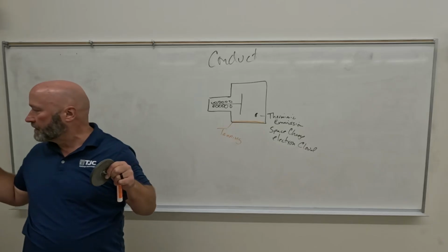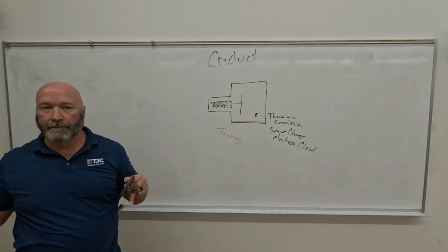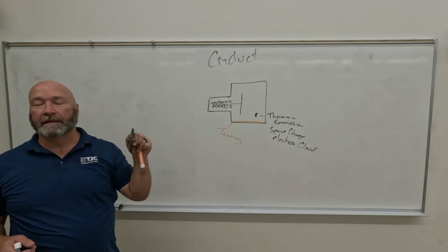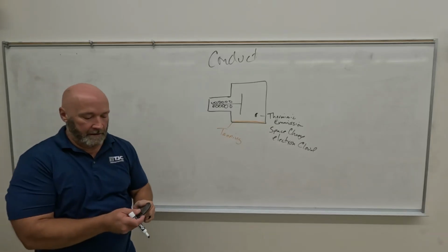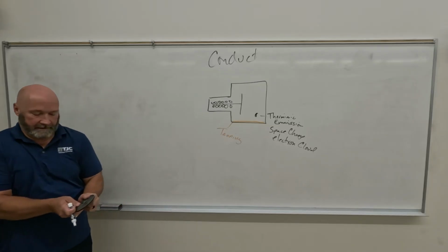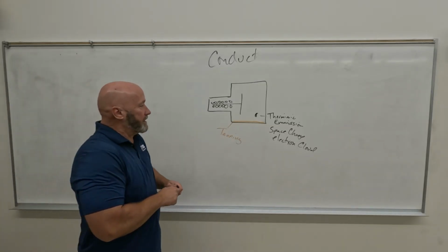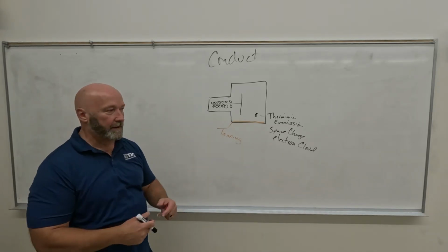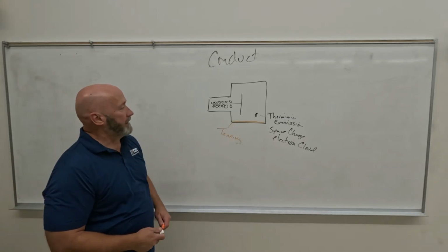Did you notice the size difference between this anode and the one in the x-ray tube? This one's a lot bigger, right? So which one do you think can hold more heat? The bigger one, right? Okay. So more on all that here in a bit. I think it's ever more going to have arrows on it. All right, so we rotate the anode in order to spread all that stuff out. Reduces the heat. So we've got tanning.